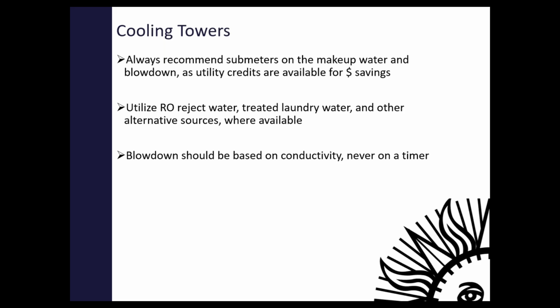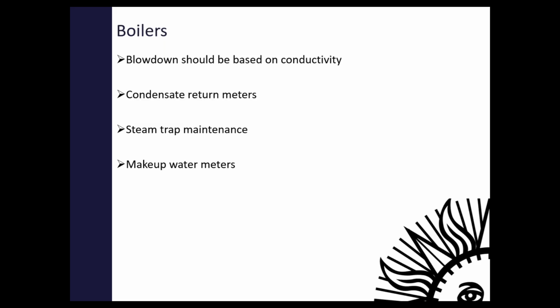And then you shouldn't ever have it based on a timer either, because that's not addressing what the situation is in your cooling tower right now, what your conductivity is right now, but rather your average, worst case scenario, which I believe is what they usually set the timer for, on a peak day. If we're running the cooling tower continuously, we need 15 minutes of blowdown. Okay, but what do you need in the winter? Probably only 30 seconds, a minute. So that's another source of water that could be saved.